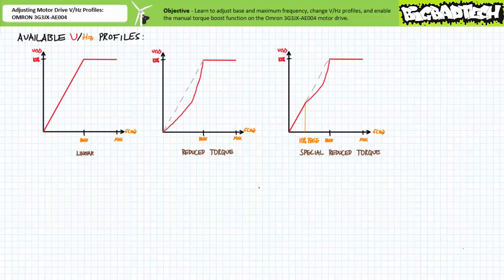This particular motor drive is not limited to solely linear volts per hertz profiles. The OMRON 3G3JX AE004 has three standard profiles available. However, one of the profiles can be altered to include a manual torque boost, so technically it has four volts per hertz profiles. The first is the simple linear volts per hertz profile we just examined. The other two are called reduced torque and special reduced torque. These profiles aren't really user customizable and are again defined by two points: base and maximum frequency. The transition point for the special reduced torque curve is continuously fixed at 10 percent of the current base frequency.